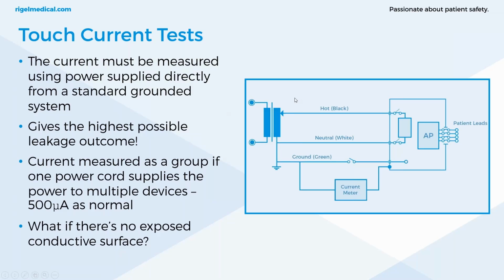Now, what I sometimes get asked over in the US for touch leakage is, where there's no exposed conductive surface, how am I going to test touch current if there's no exposed conductive point? Well, in previous revisions of NFPA 99, now this has disappeared, but it's still mentioned in IEC 60601, you can simulate an exposed conductive point by placing a 10 by 20 centimeter metal foil in contact with that exposed surface.